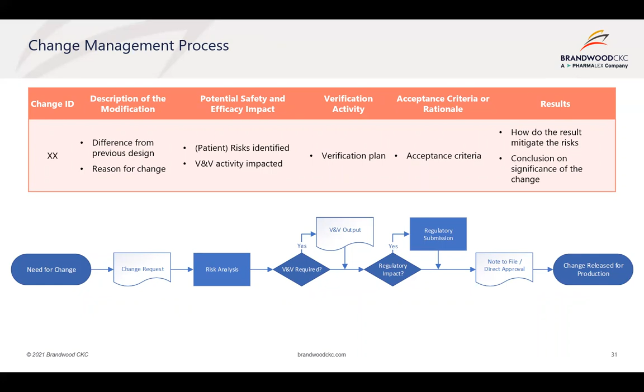You identify either by way of regression or by way of a risk assessment, what's the impact of that change and what might be the implications to the patient, but also in terms of the impact to your verification and validation activities. So obviously you're going to be changing, for example, the product specification. That's going to flow into some of the documentation updates that you need to make, but also in terms of repeating possibly certain tests that you have to repeat in order to verify implementation. The verification activities must also be documented for the implementation of that change with very clear acceptance criteria and rationale, and obviously your results. So if you maintain a history of changes documented in this fashion, that's going to help you putting together regulatory applications down the line.